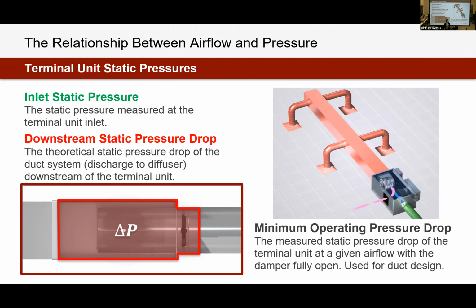This is another device in our duct system that has a pressure loss associated with it. So we need to make sure that we're sizing our air handler to overcome the pressure loss of all of those terminal units in the system. Again, the takeaway here, inlet static pressure has to be greater than the sum of all downstream losses to get any air to flow.